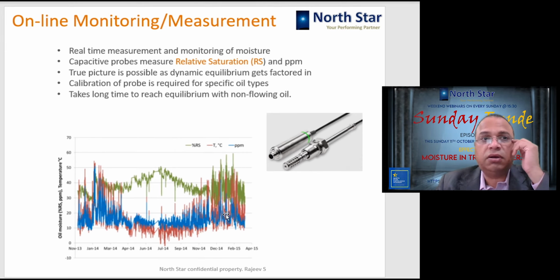The second method is online monitoring measurement, where a probe is put in the pipeline or in the transformer, and this probe measures the ppm continuously. These are capacitive probes, and because they are present inside the transformer in that environment, they are also able to capture the equilibrium condition, that is relative saturation. They are able to monitor that, and that gives you the true picture.